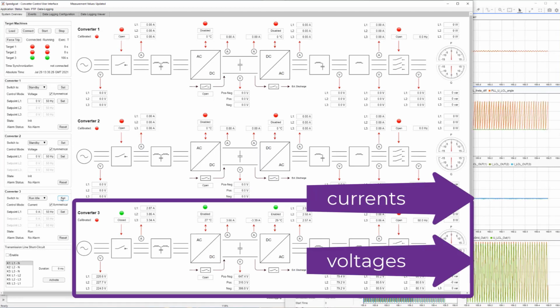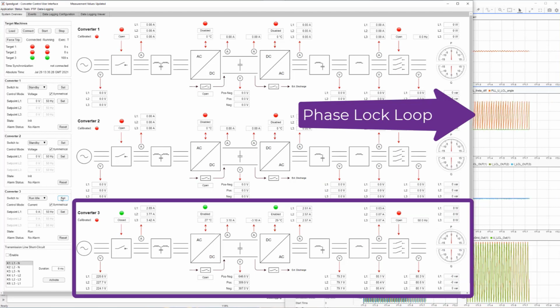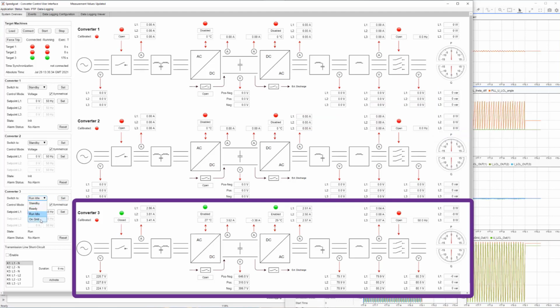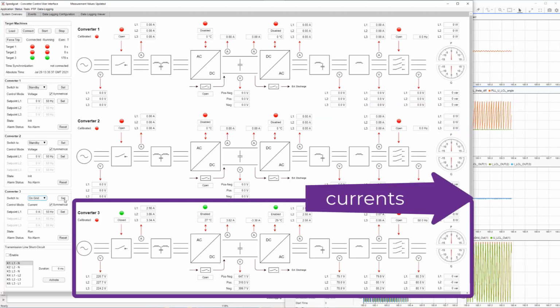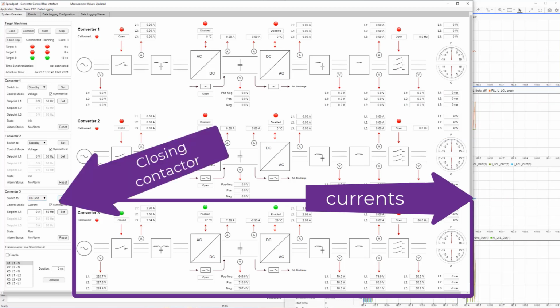Before closing the contactors, we let the phase lock loop synchronize to the grid provided by the power amplifier. Then we'll close the contactors and connect to the virtual grid. Failure to synchronize correctly would result in large currents, potentially damaging the equipment. We synchronize and gradually increase the current.